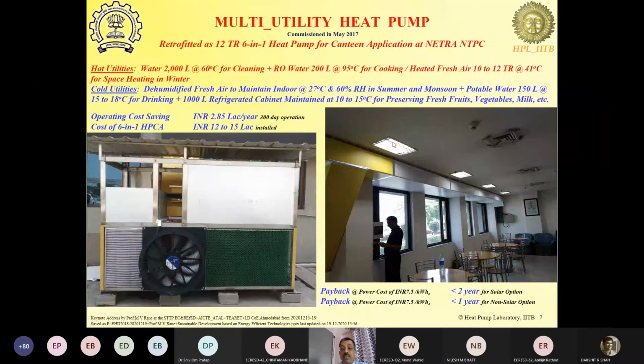At these conditions, for summer and monsoon, we would supply air to maintain the indoors at 27 and 60. So the actual air supplied will be lower than this. Typically 21 to 22 degree air will be supplied into the zone. And then the second utility is the hot air that is supplied in winter.